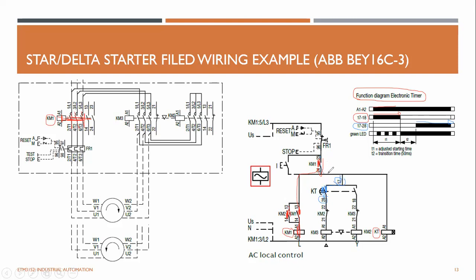Now the current can come from here through here, and KM3 is energized. This is KM3. Once KM3 is energized, this one will be open, so it is interlocked, which means no one can connect it back to the star connection. This is interlocked. This is completed, so you can see the wiring diagram for reference. So it will become a delta connection.